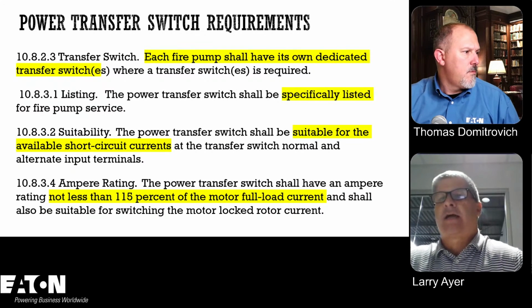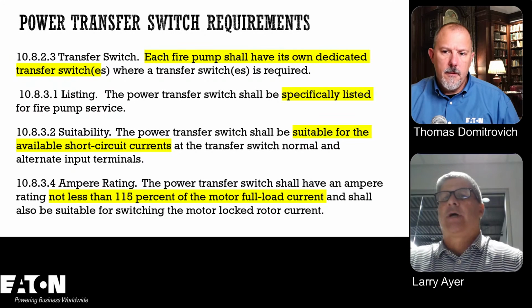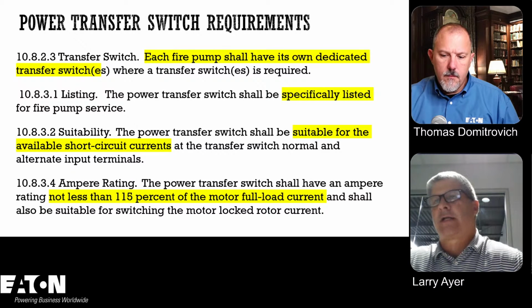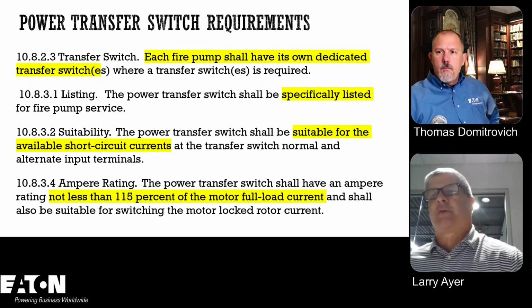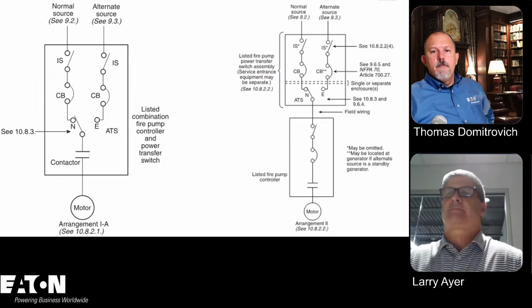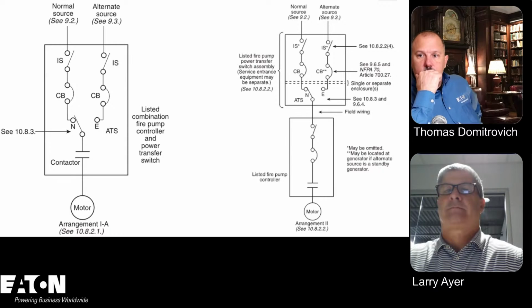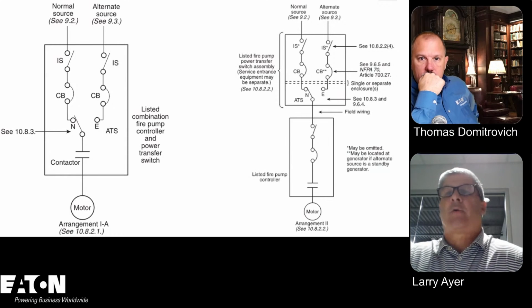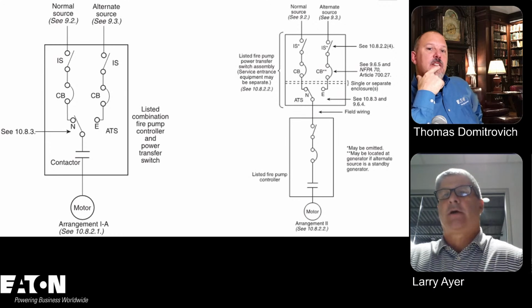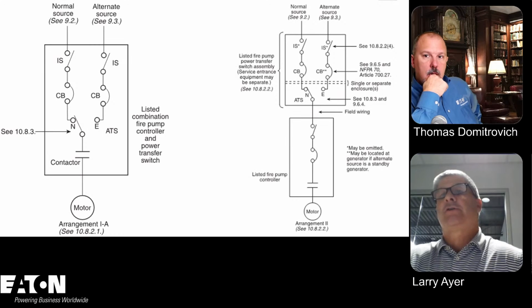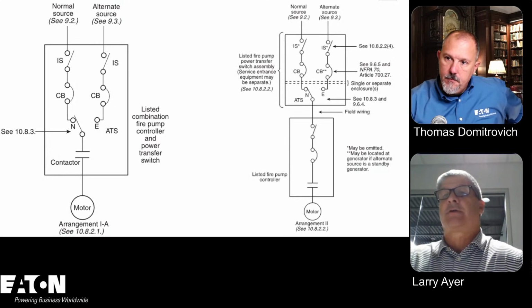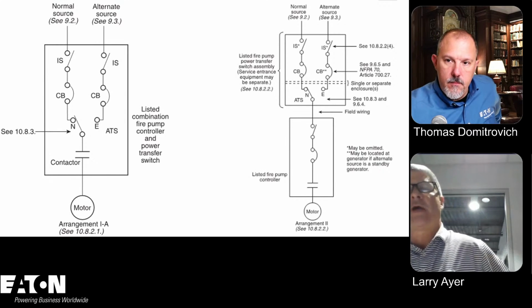So you might have 115% rated for motor full load current, but these things typically have a significantly higher fault current rating, so they should be able to handle that locked rotor current for a specified period of time. So these are a couple good images, and this is kind of a couple ways you can handle transfer switches if you need an alternate source of power. The one on the left has a fire pump controller and a power transfer switch built in the same enclosure. Or you could do the one on the right. You could have a fire pump transfer switch in a separate enclosure, and also a listed fire pump controller. So there's a couple ways you can do that.